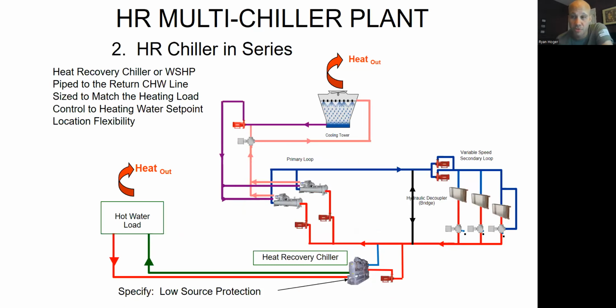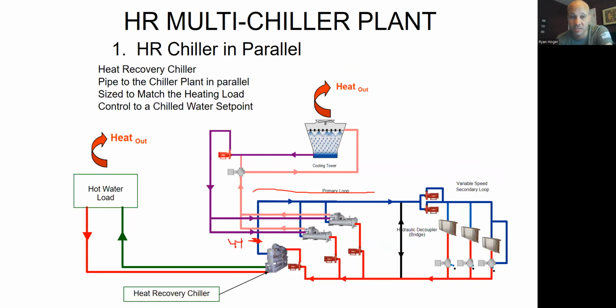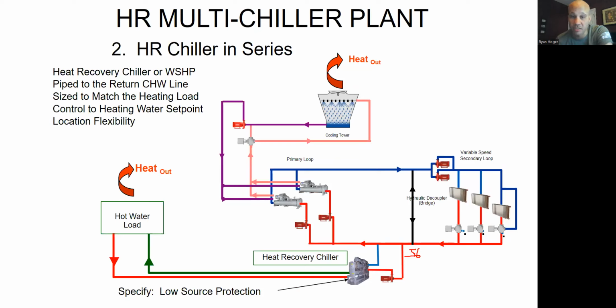Here, I don't care what temperature the chilled water is. I've got 56 coming back. If this chiller is so tiny compared to these guys, and all he does is cool the 56 down to 54, cool. That's 2 degrees of free cooling that I just got for the other guys. It's going to be waste cooling now instead of waste heat. In this case, I'm taking the waste heat and using it to heat something else up. I'm running this chiller as a heater to maintain whatever 130-degree water is going out to this load. And I have waste cooling over here. It's kind of a different, weird way to look at it, but it allows me to control the heating load more precisely.